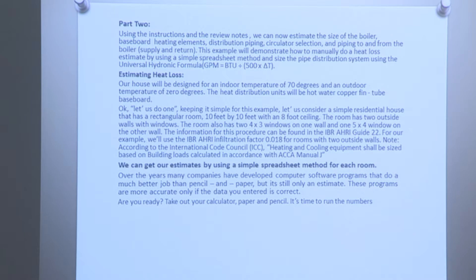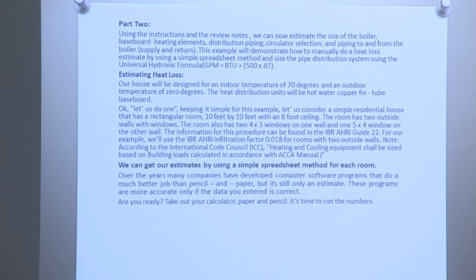For our example, we'll use the IBR AHRI infiltration factor of 0.018 for rooms with two outside walls. Note: according to the International Code Council, heating and cooling equipment should be sized based on building loads calculated in accordance with the ACCA Manual J. We can get our estimates by using the simple spreadsheet method for each room. Over the years, many companies have developed computer software programs that do a much better job than paper and pencil, but it's still only an estimate — these programs are more accurate only if the data you enter is correct. Are you ready? Take out your calculator, paper and pencil. It's time to run the numbers.